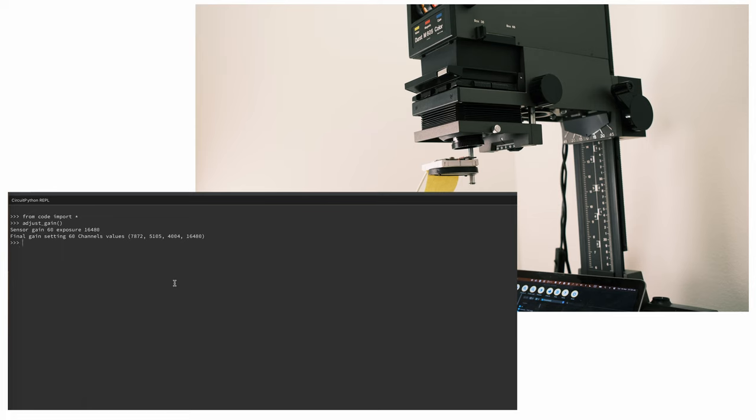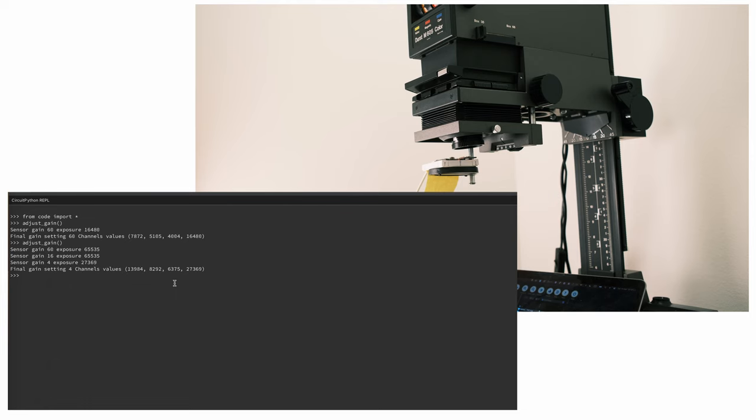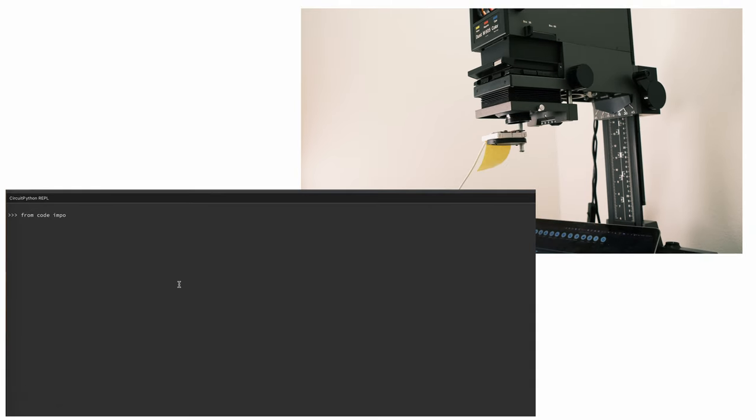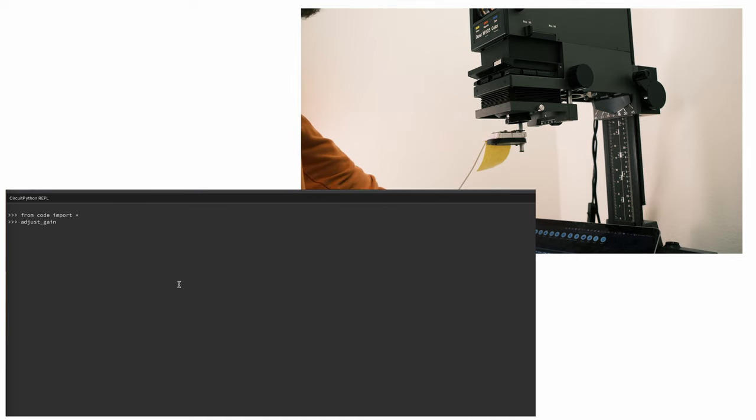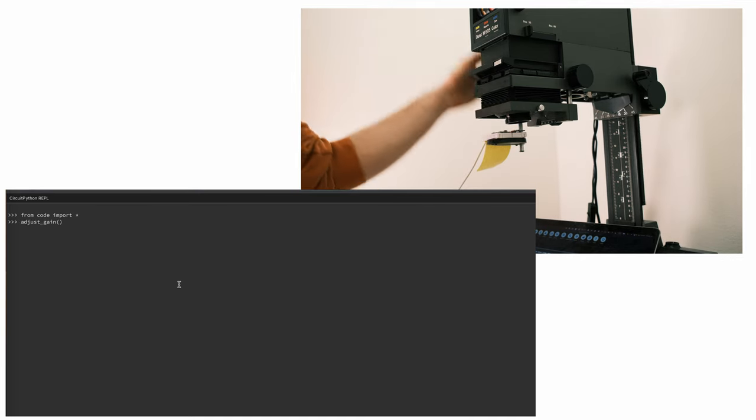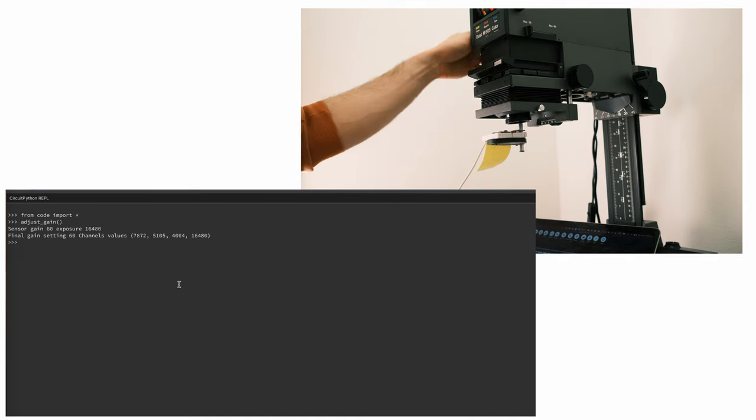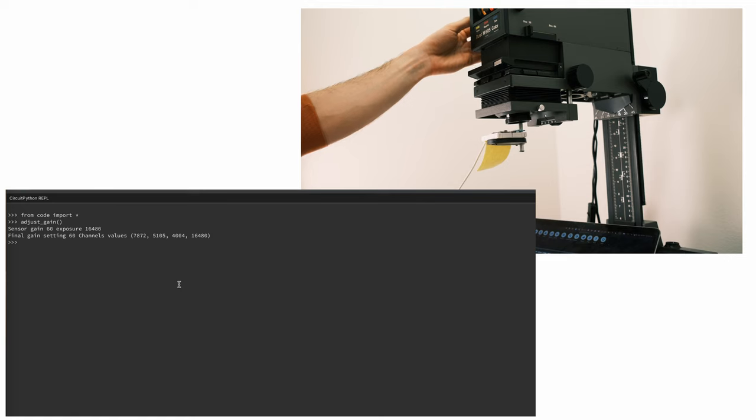Each time when you change the filters you actually change exposure also. I recalibrated again and now I can also calibrate the correction for each channel to the exposure value, making each channel relative to exposure and basically aligning all the channels in the signal.